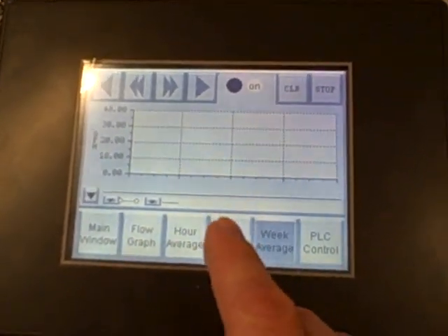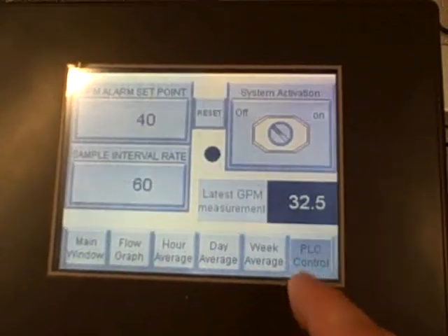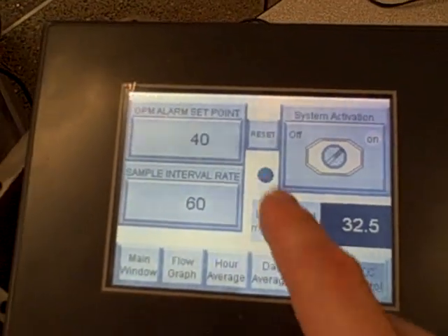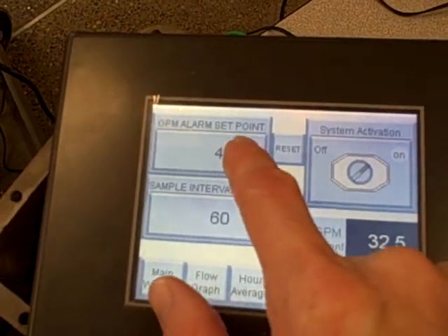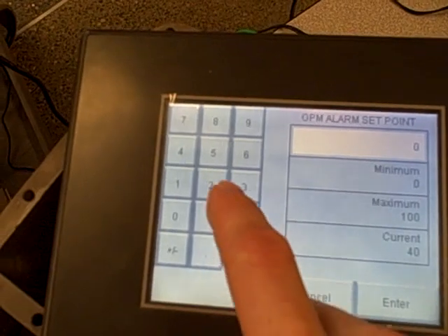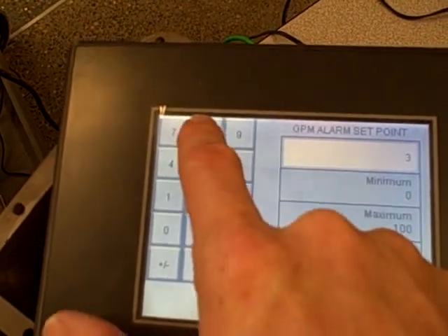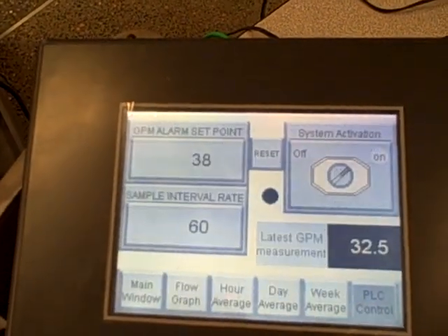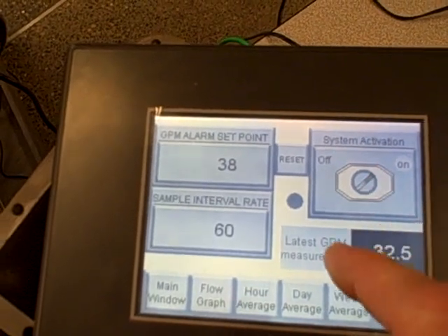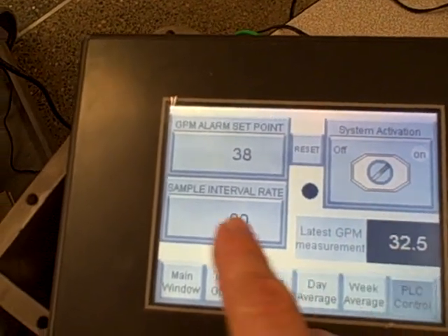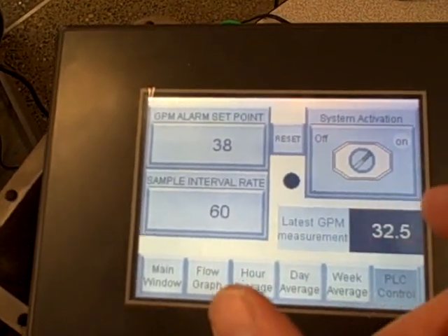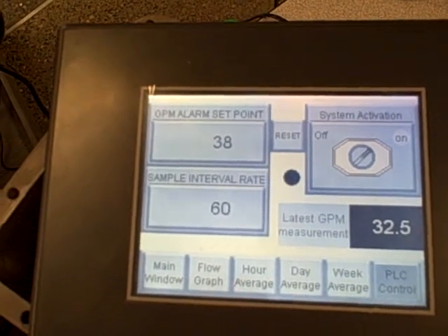And presently we have no data for the day and weekly flows because we have not had the system running that long. We can also set the water flow alarm. If we want the alarm setpoint to be at a different value, we can actually type in a different value. I'll set it for 38 gallons per minute instead of 40. We can activate and deactivate the system.